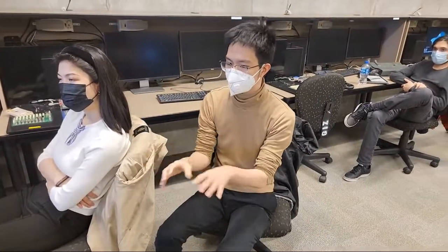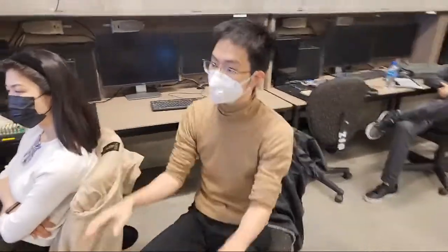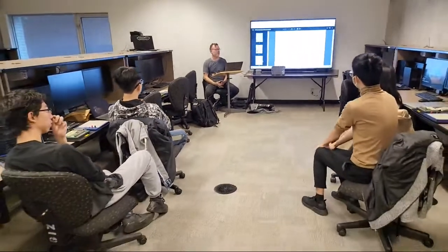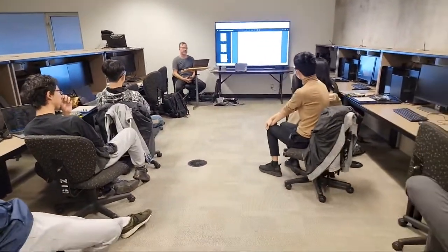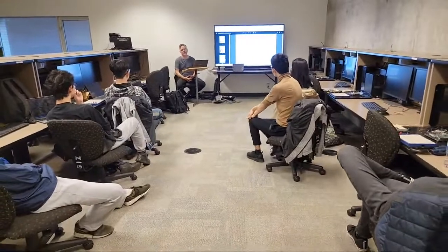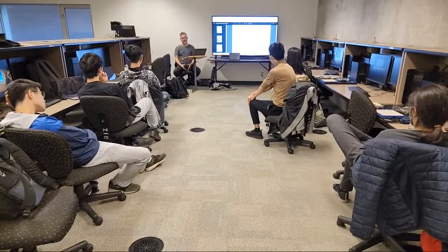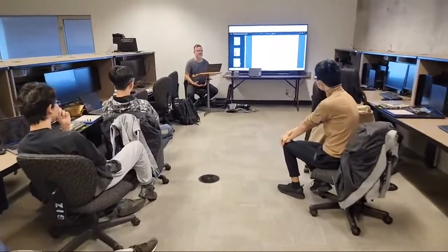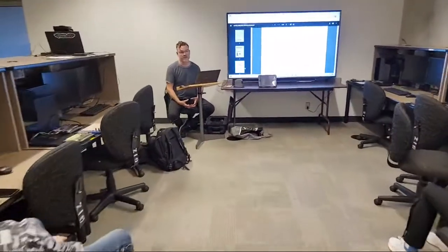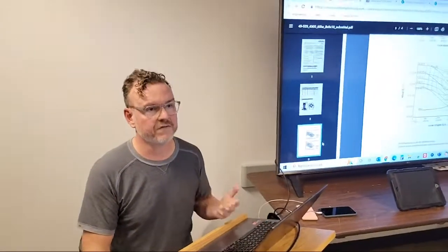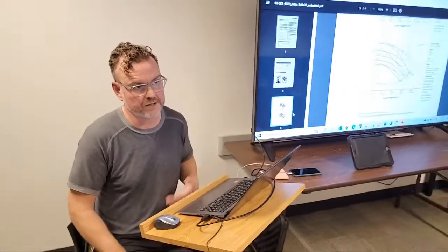But have you considered integrating that maybe into the whole virtual reality thing? 100%, absolutely. Anything with a compressor, like VRF, variable refrigerant volume, chillers, is going to come with the microprocessors already embedded and factory wired, because they're managing the vapor compression cycle, right? They're also managing the health of the compressor and the safe and efficient operation of the machine, right?